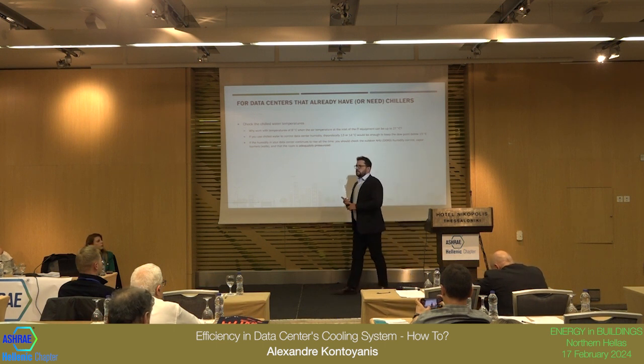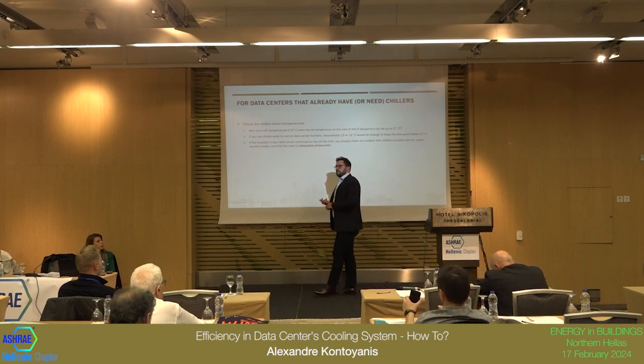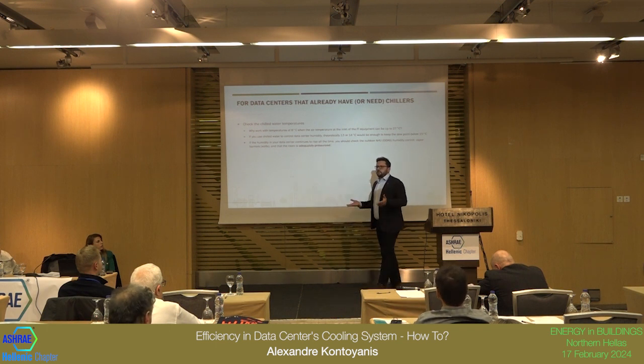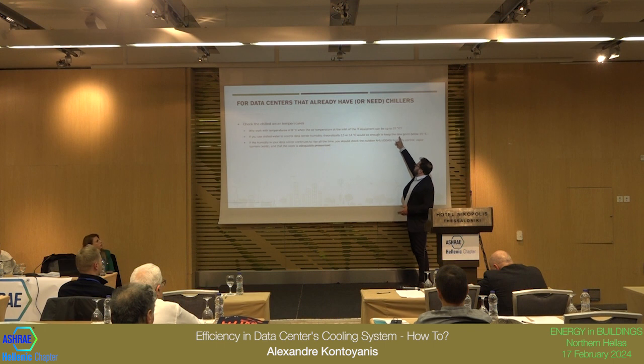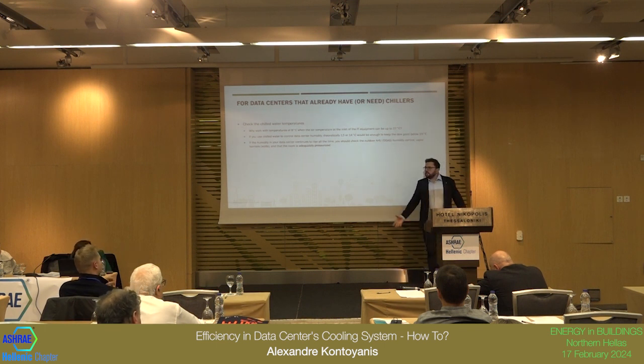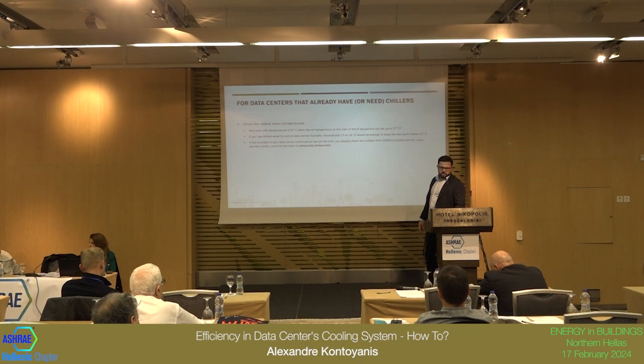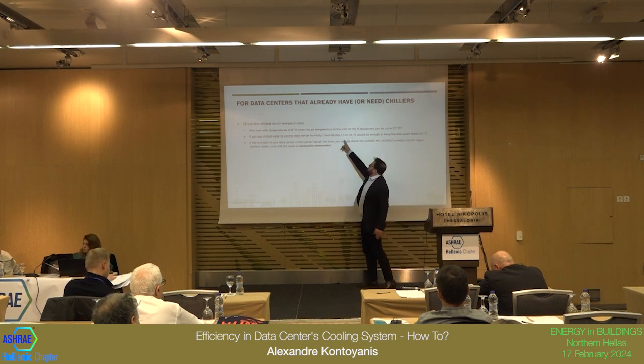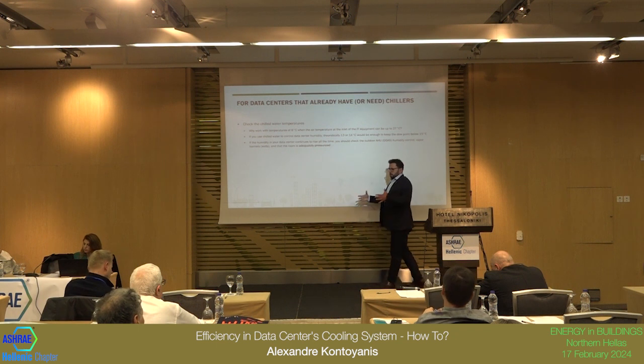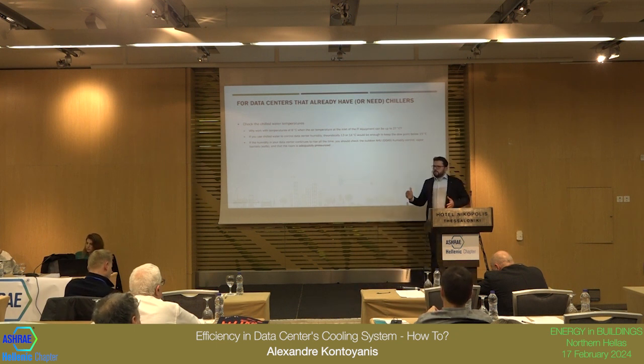In many of the data centers that I visit, chiller water temperatures are around 8, 9 degrees. Why operate that cold if your IT can take up to 27? You should raise it to 12, 13, and save some energy on chillers. They say they use chilled water to control the humidity. Theoretically, if you run around 13 degrees, your coils control the humidity below the 15 that we recommended as ASHRAE. So you don't need to run at 8.